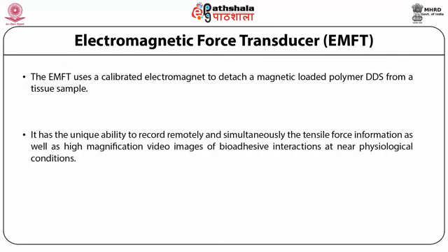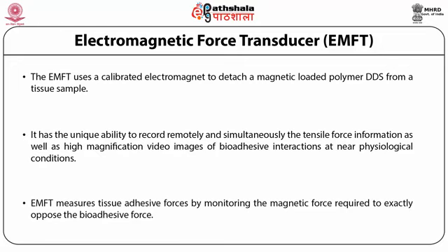It has the unique ability to record remotely and simultaneously the tensile force information as well as high magnification video images of bioadhesive interactions at near physiological conditions. The EMFT measures tissue adhesive forces by monitoring the magnetic force required to exactly oppose the bioadhesive force.